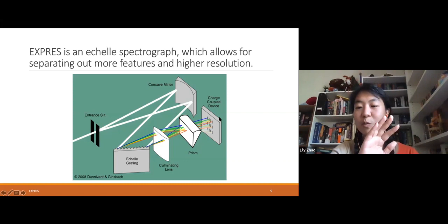So here's EXPRES in its lovely, cozy little vacuum chamber. EXPRES is environmentally stabilized in this vacuum chamber, which allows it to be passively temperature controlled. It has 3 levels of vibrational isolation. So the optical bench here, which contains all the mirrors and the prisms, is vibrationally isolated from the vacuum chamber, which is then vibrationally isolated from the floor. And the floor itself is actually vibrationally isolated from the telescope. So we poured an independent concrete slab so that when the telescope moves, the vibrations from the dome movement and things like that won't transfer to the instrument.